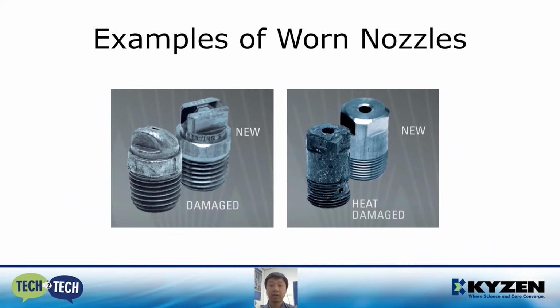If the nozzle suffers the above conditions, the pressure gauge reading will drop as it loses pressure through the nozzle tips that may have widened due to wear. So in such a condition, replacing with a new nozzle will be the only option.